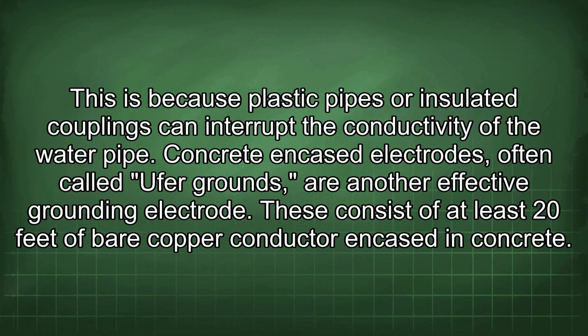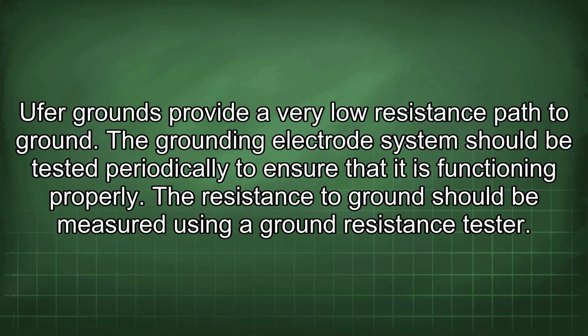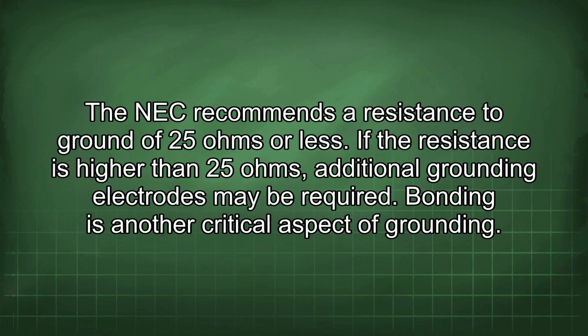Concrete encased electrodes, often called UFER grounds, are another effective grounding electrode. These consist of at least 20 feet of bare copper conductor encased in concrete. UFER grounds provide a very low resistance path to ground. The grounding electrode system should be tested periodically to ensure that it is functioning properly. The resistance to ground should be measured using a ground resistance tester. The NEC recommends a resistance to ground of 25 ohms or less. If the resistance is higher than 25 ohms, additional grounding electrodes may be required.